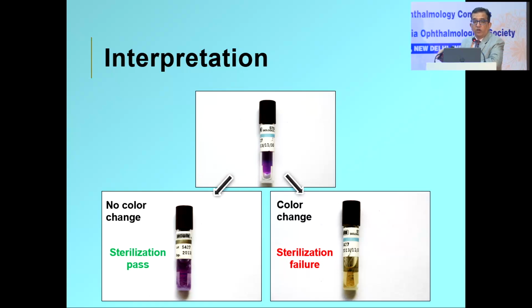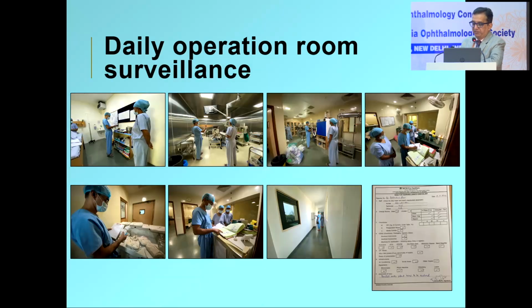If your sterilization process is good, that means all the spores would have been killed, so there won't be any change in this media indicator. However, if there is a lapse in this sterilization, the pressure has not reached, or if the steam has not penetrated, then the spores would not die. So once you crush it and incubate it, then the spores would turn into bacteria, and then you'd get a color change. So you just need to look for the color change. However, just doing this is not enough. Although this is not the microbiological surveillance, this is an operation room surveillance.